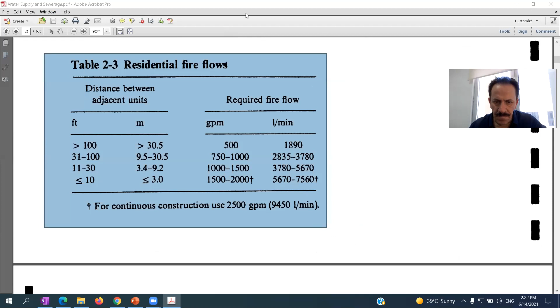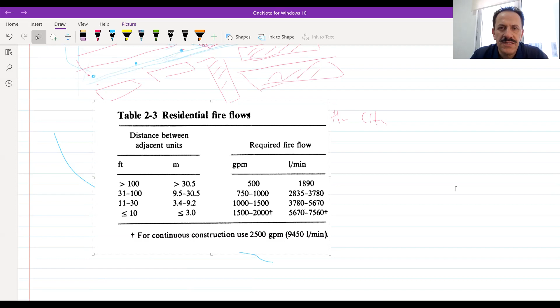Here's the table. This table will tell us what additional quantity of water is needed for the building. And later we will start. There are two equations for calculating the amount of water needed for every standard fire. Besides this amount, which is essentially for fighting a fire, we need more water. This is for an adjacent building. If there is a building here, we allocate fire demand for this building, and there are two equations for that.